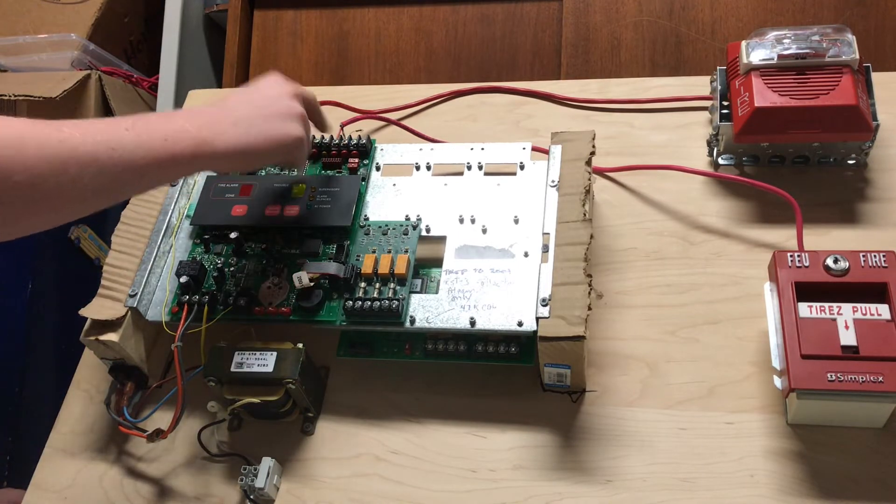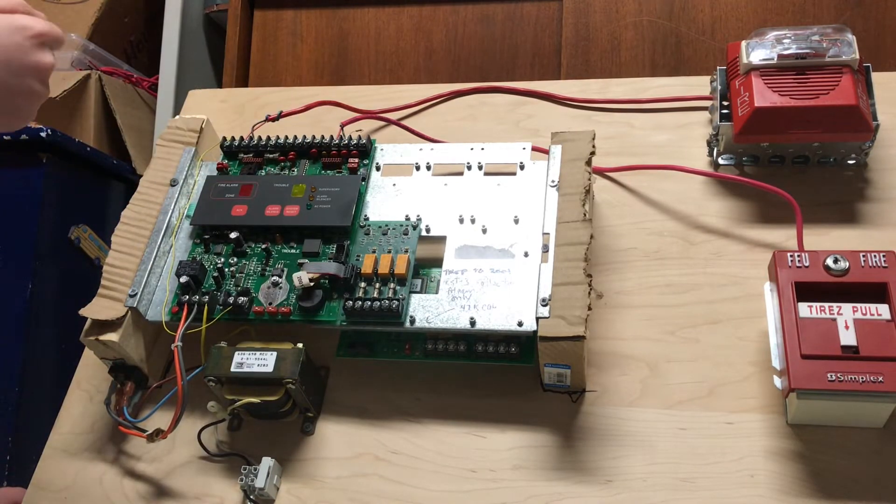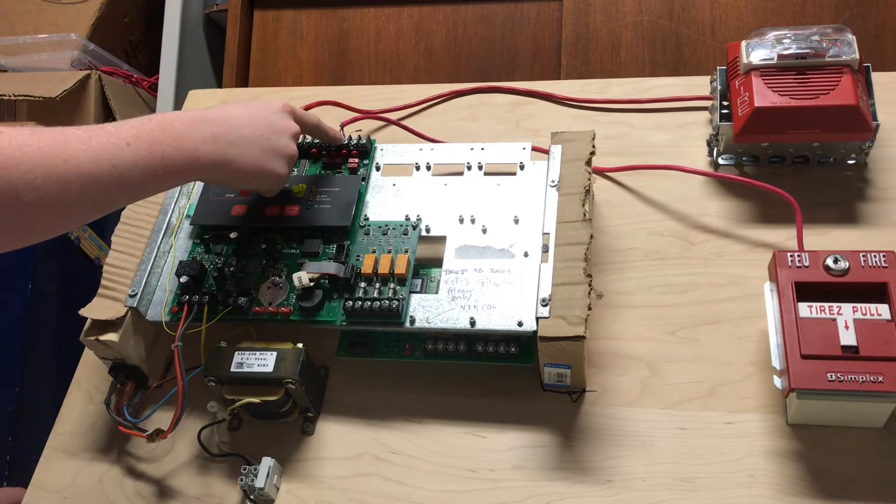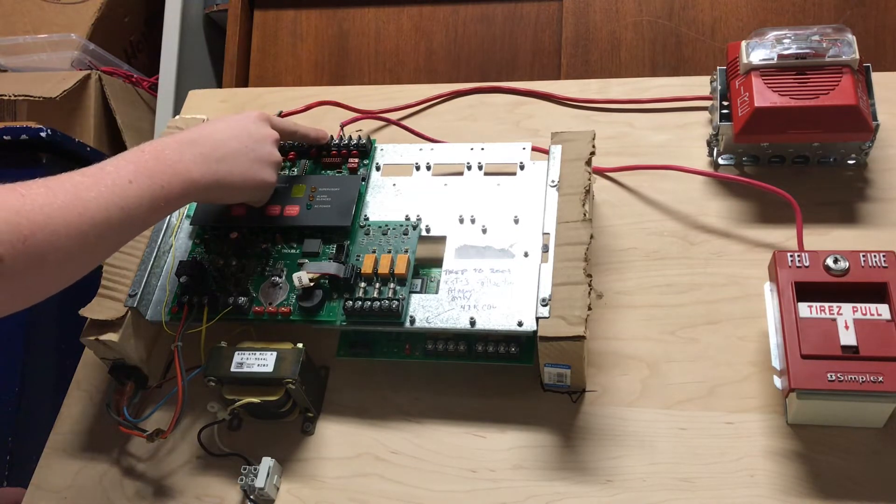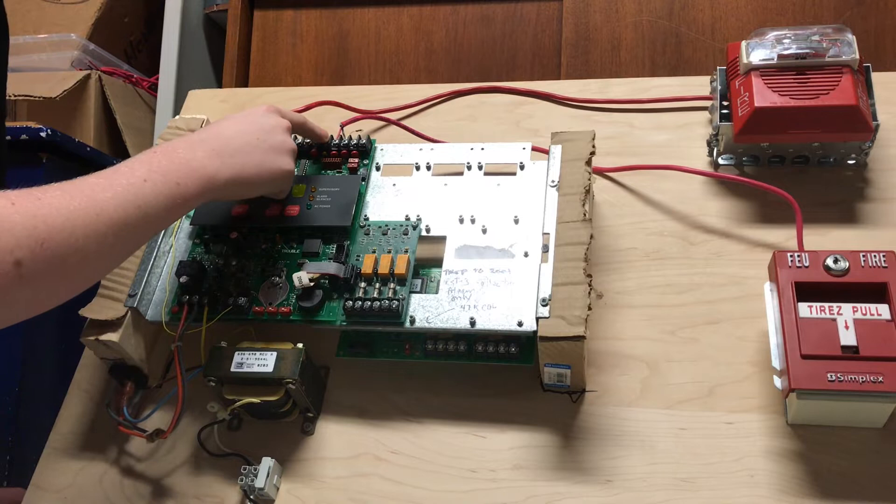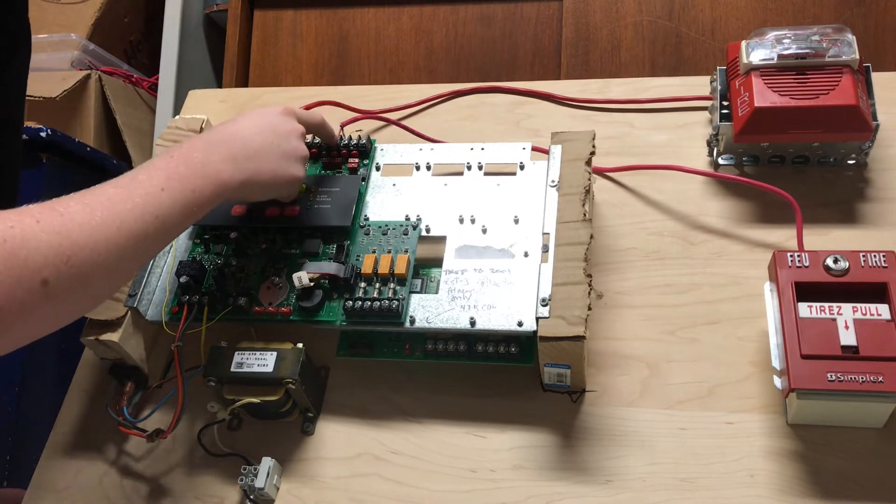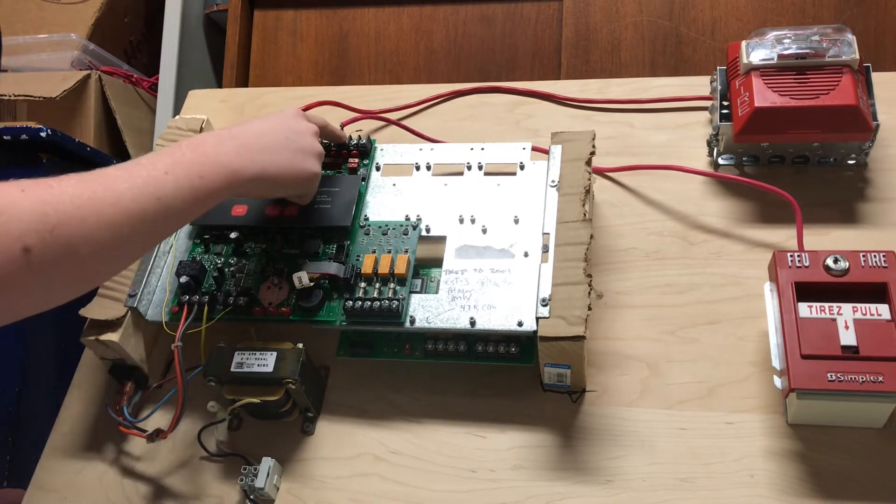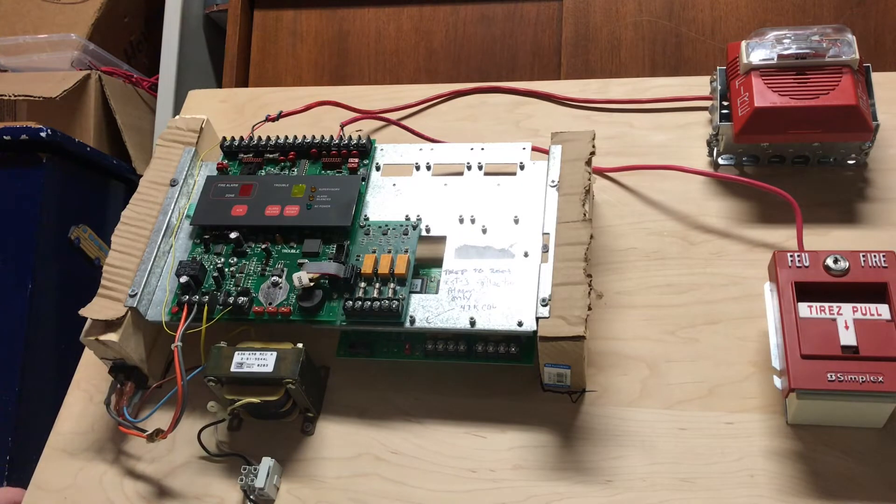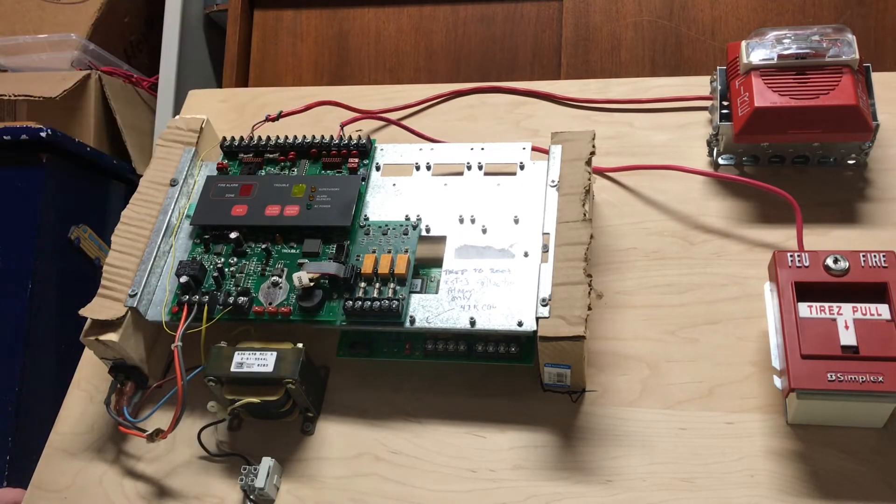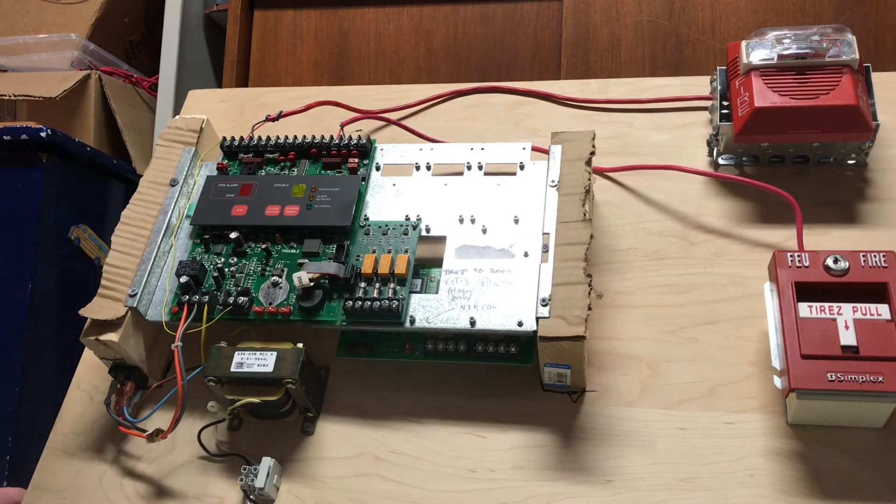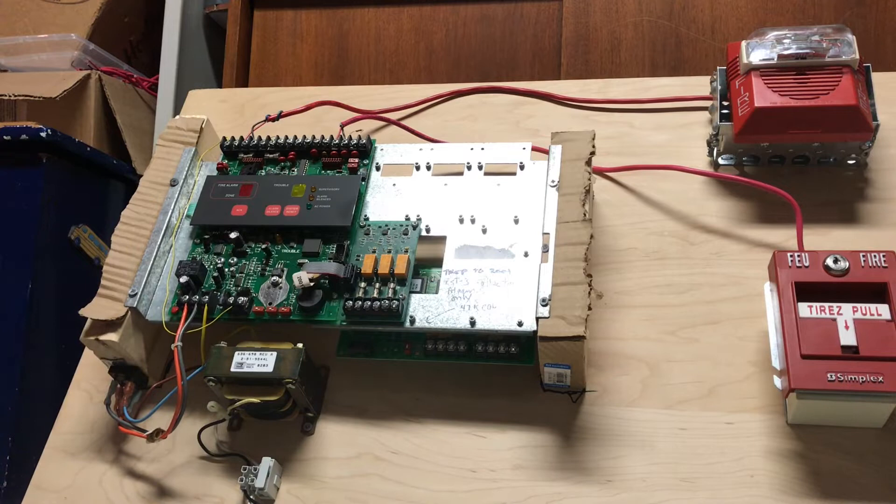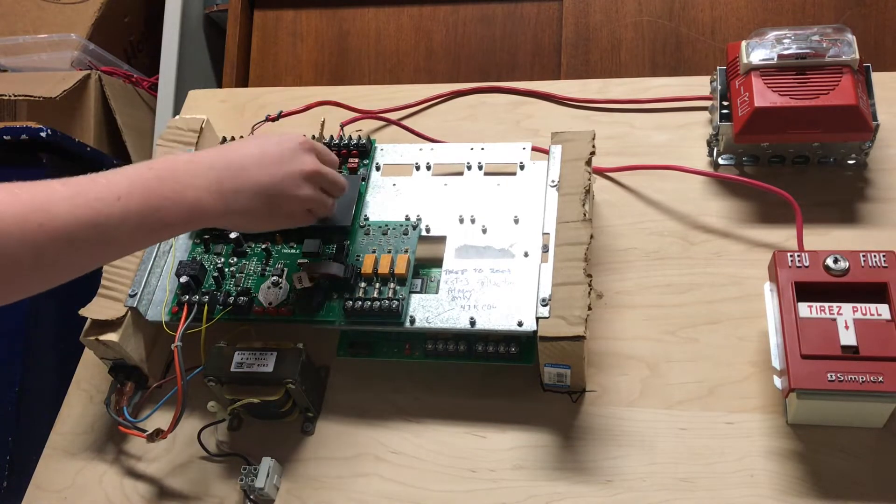The zone terminals are actually kind of interesting because here, you have zone one and zone two, but each zone has three terminals labeled AUX, RET, and zone power. Basically, how this works is that each zone, both zones one and two, share the negative terminal. I'm not really sure why they did that. It may have just been to keep costs low.